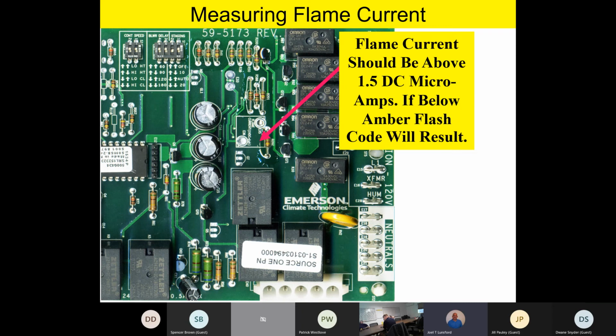Now write this down and remember it. Amber flash code starts occurring at 1.5. The furnace will continue to run all the way down to 0.1 microamp flame current. So that's very, very low, 0.1. It'll continue to run. So our lockout point is 0.1. 1.5 is where we generate an amber flash code to let you know, hey, the flame current's getting low.